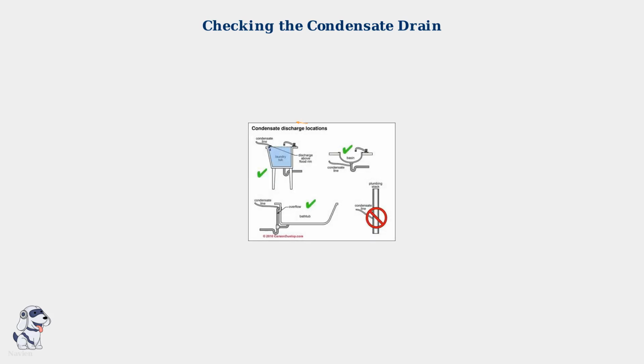Checking the condensate drain is an important troubleshooting step. A clogged drain can cause your tankless water heater to shut down, so visual inspection is key. The condensate drain line is typically PVC pipe connected to your unit, draining to acceptable locations like a laundry tub, basin, or bathtub above the overflow point.